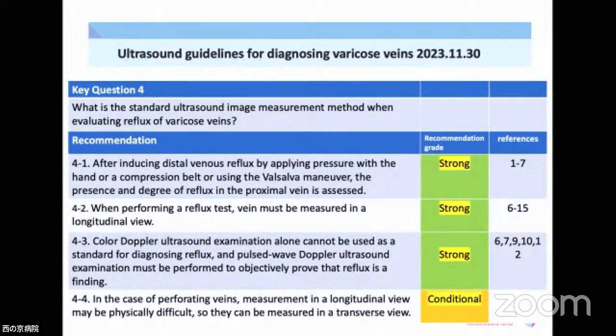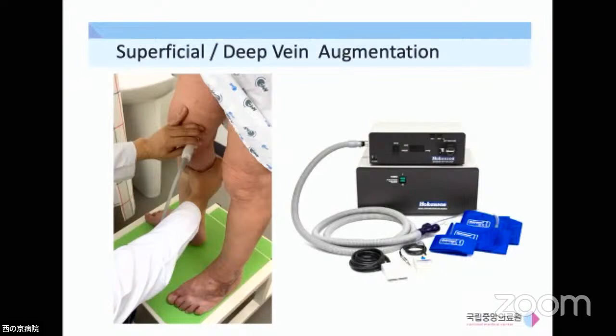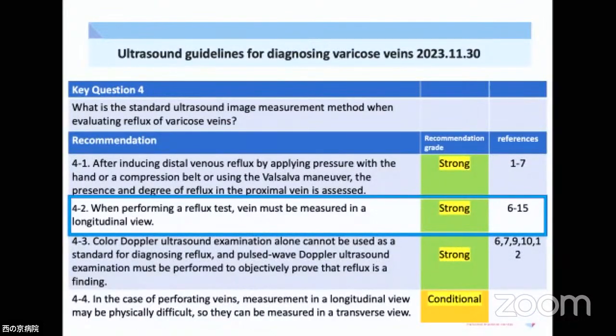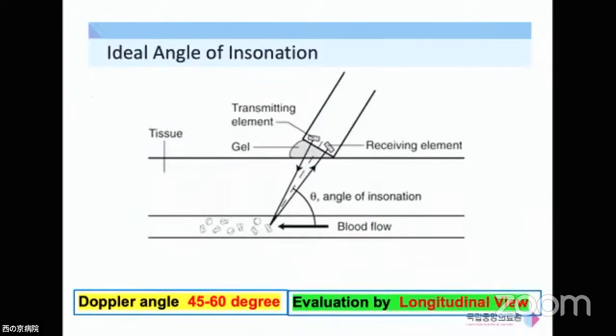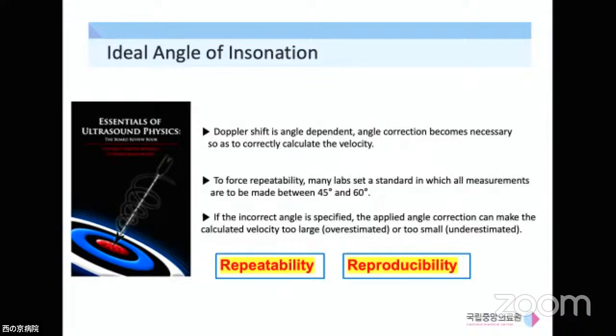Key question 4. We should check the augmentation by muscle squeezing or a pneumatic compression device. When performing a reflux test, a vein must be measured in longitudinal view. Because of time limit, I'll skip this. In particular, when the angle is greater than 70 degrees, the measurement error rate appears to be extremely high. So when observing a blood vessel, longitudinal view measurement should be made with a Doppler angle of 45 to 60 degrees, for the repeatability and reproducibility of the examination.